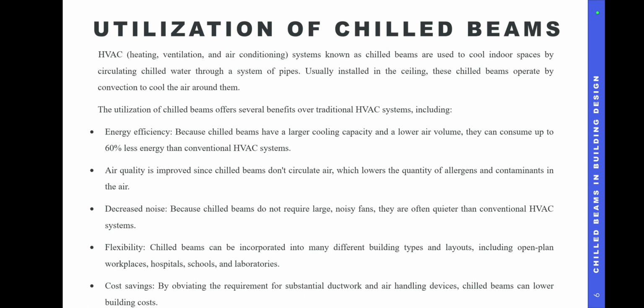These chilled beams operate by convection to cool the air around them. The utilization of chilled beams offers several benefits over traditional HVAC systems, including energy efficiency, because chilled beams have a larger cooling capacity and a lower air volume. They can consume up to 60% less energy than conventional HVAC systems.